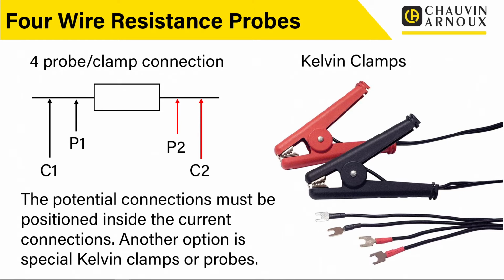So we would position those outside of the sensing contacts, of the potential contacts. So we connect C1 and C2 on the outside, and then inside of that, we would connect the sensing circuit, the potential circuit, P1 and P2. So the current travels round, we're then measuring inside of that, and that's where we take the measurement.